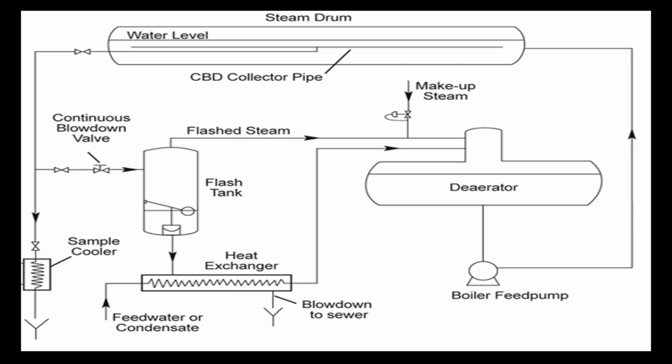In other words, we want to scrub that clean. And in the deaerator, we're removing CO2 and O2 and any other dissolved gases that are in there. The other one that sometimes pops up, depending upon where we're getting the water source from, could be ammonia as well as a dissolved gas.